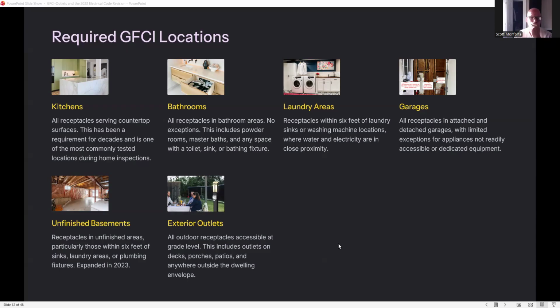Laundry areas, receptacles within 6 feet of laundry sinks or washing machine locations, where water and electricity are in close proximity. Garages, all the receptacles in attached and detached garages, with limited exceptions for appliances not readily accessible or dedicated equipment. Unfinished basements, receptacles in unfinished areas, particularly those within 6 feet of sinks, laundry areas, or plumbing fixtures, expanded in 2023. And exterior outlets, obviously, all outdoor receptacles accessible at grade level. This includes outlets on decks, porches, patios, and anywhere outside the dwelling envelope.